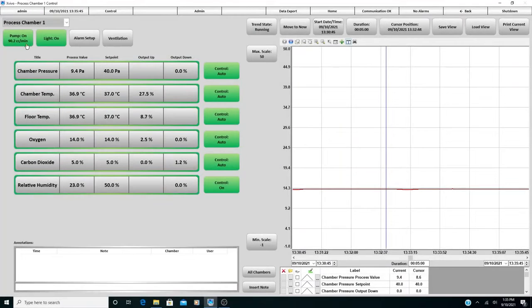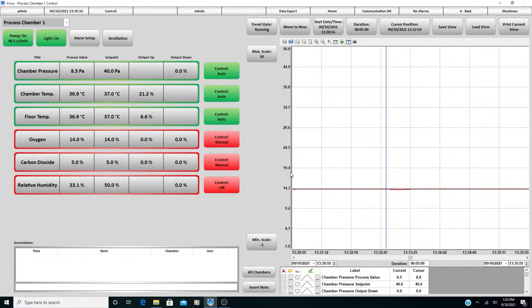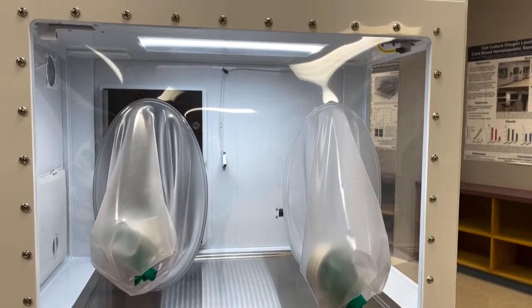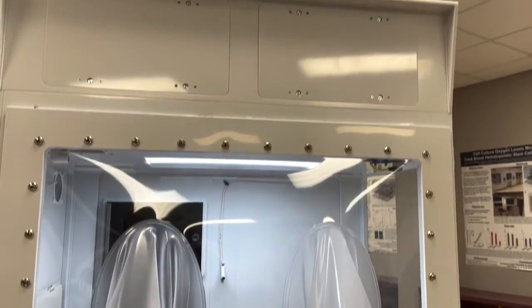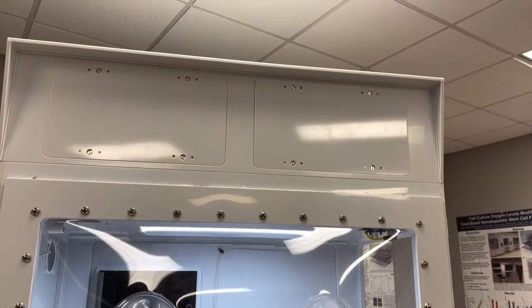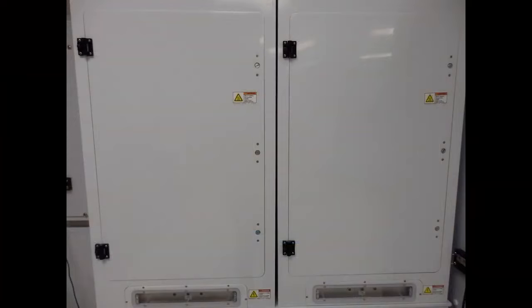Once you have received the replacement sensor pod, turn control off in the module where the sensor pod is being replaced. Locate the enclosure panel the sensor pod is located behind, usually above the module where you are changing the pod. Incubator sensor pods are located behind the access door on the back of the incubator.